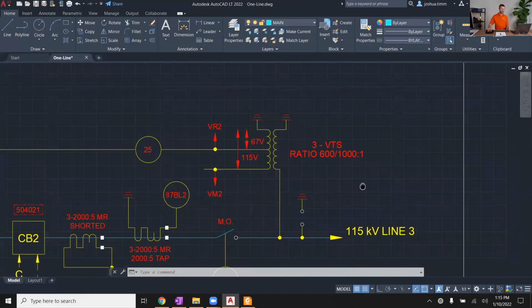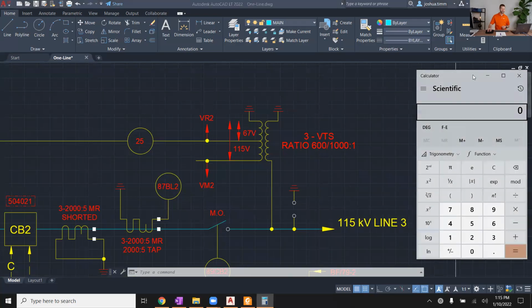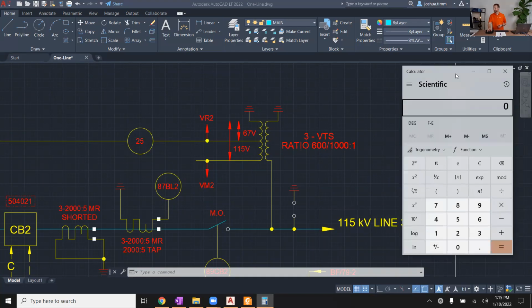How would you gut check that if this is a 115 kV line? This is a good PE exam question for junior engineers, EITs out there. This is a 115 kV line. That's a line to line quantity by convention. So 115,000 divided by root 3, square root of 3, 1.73 gives us about 66 kV line to neutral. And then remember the 67 volt tap is 1,000 PT ratio. So we divide that by 1,000 and we get 66.5, or you can round up to 67 volts on the secondary. So that kind of gives you a gut check that we picked the right ratio with the right tap.